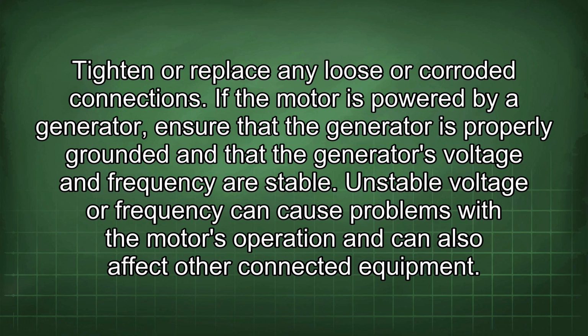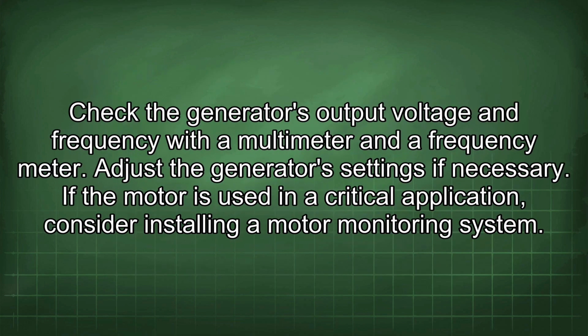If the motor is powered by a generator, ensure that the generator is properly grounded and that the generator's voltage and frequency are stable. Unstable voltage or frequency can cause problems with the motor's operation and can also affect other connected equipment. Check the generator's output voltage and frequency with a multimeter and a frequency meter. Adjust the generator's settings if necessary.